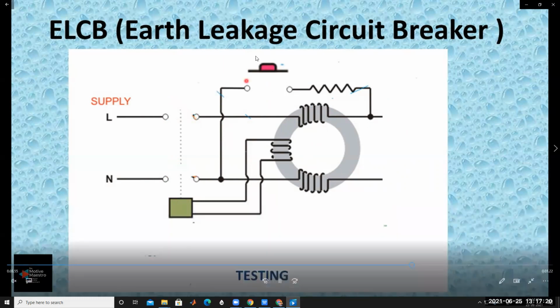It's clear. And then, how to test the ELCB? Coming to the testing of the ELCB: how to test whether the ELCB is working properly or not? By removing the load. So remove the load here; don't connect the load. This switch is called the test switch. Under testing condition, this switch is closed, and this line is also closed, like this.